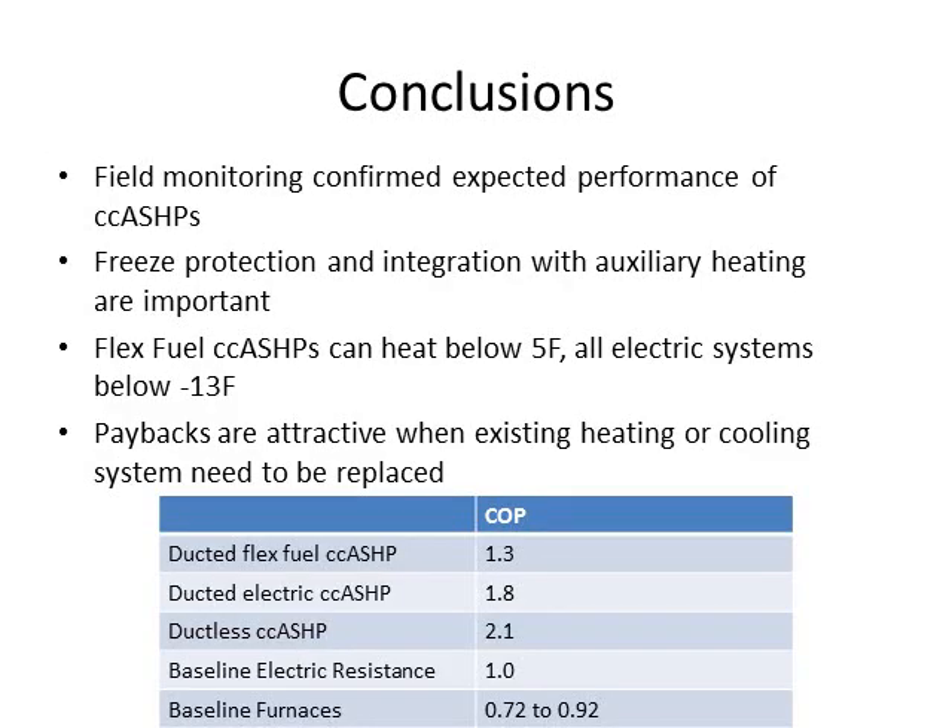Overall conclusions: field monitoring confirmed the expected performance of these heat pump systems. Freeze protection and integration with backup heating systems are very important and can greatly affect COPs. The Flex Fuel heat pump systems can heat below 5 degrees and the all-electric systems below negative 13 degrees — the technology has advanced to allow heating at lower and lower outside air temperatures, especially important in Minnesota. Paybacks are most attractive when existing heating or cooling systems need replacement. Annual COPs: ducted Flex Fuel at 1.3, ducted electric at 1.8, ductless at 2.1, versus baseline systems at 1 or below.